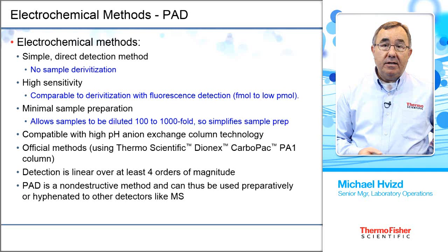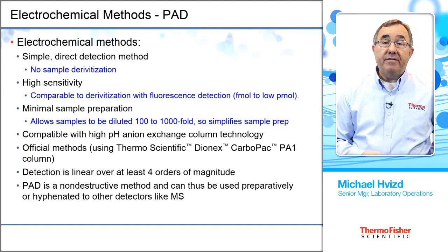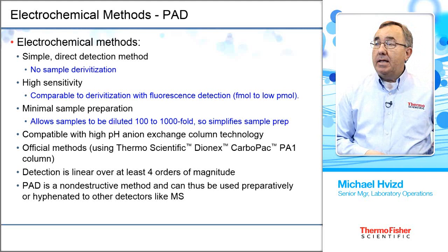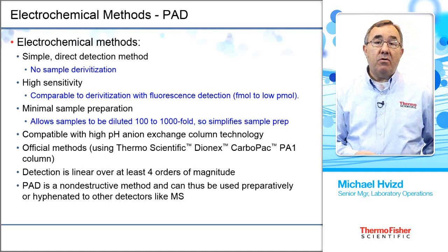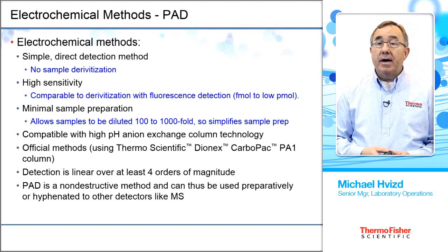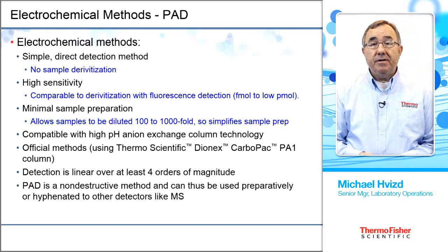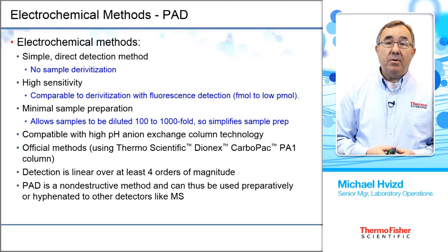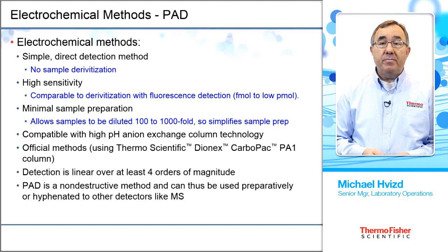We can dilute our samples by a factor of 100 or even 1,000 and still have very good sensitivity with this detector. Most of our methods developed over the years are now official methods in the AOAC or other groups. Detection is linear over four orders of magnitude. Since PAD is a non-destructive technique, we're able to take a fraction of the sample as it comes through our detector and use it in other instrumentation, such as a mass spectrometer.